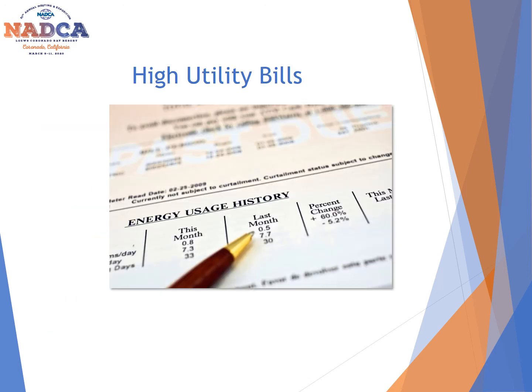Now, the obvious thing to consider anytime an HVAC unit is working longer and harder because the air is leaking into unoccupied spaces or areas that you don't want it to, is that the system is going to cost more. It's going to cost more electricity. Therefore, your bills are higher. So if we can decrease even a small percentage of the amount of air that's being leaked into a facility, we can act.